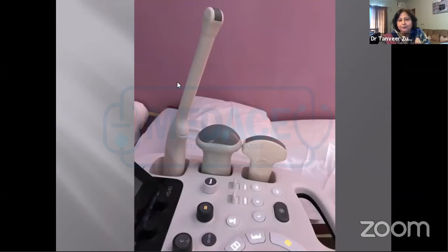These abdominal probes need a low level of disinfection after every patient. This is normally done. Whatever we are doing now, we are a bit more extra careful, but this is routine and should be done routinely. After every patient, these probes should be cleaned, and then wiped with a damp cloth for the next patient. But the transvaginal probe needs meticulous cleaning. It needs deep, high-level disinfection, and what we do normally still applies, but at this time of pandemic we have to be very, very careful that it is cleaned daily.